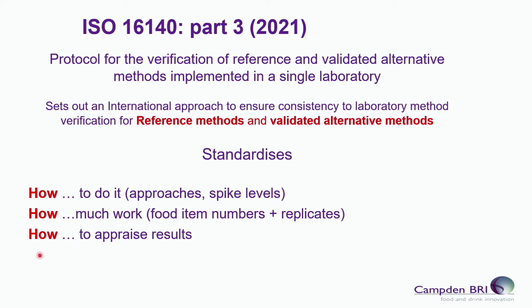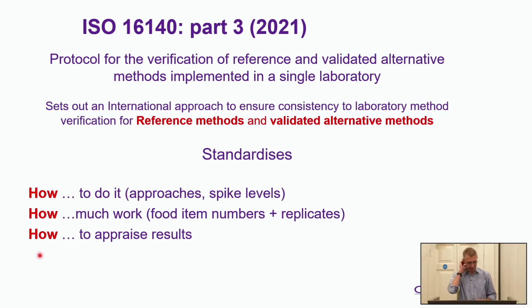When we move to verification, so this is the methods that you use in your lab, it doesn't matter whether you're using an ISO reference method or whether you're using a proprietary method, they have to be verified. All of them do. You have to do this in your own laboratory. So this is what 16140 Part 3 is doing. And what it does, it standardises how to do verification.